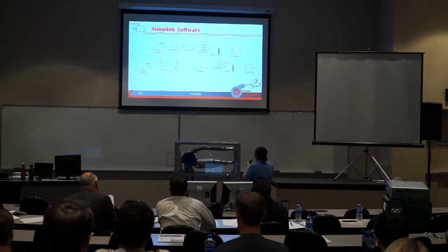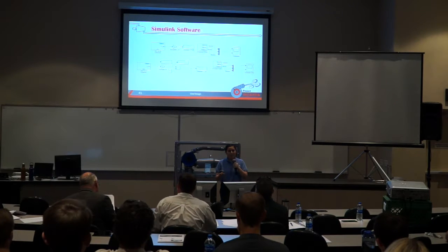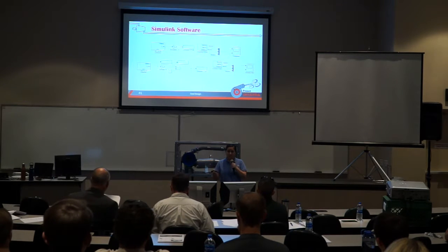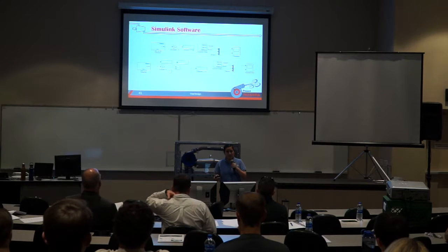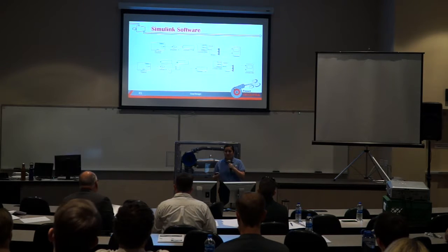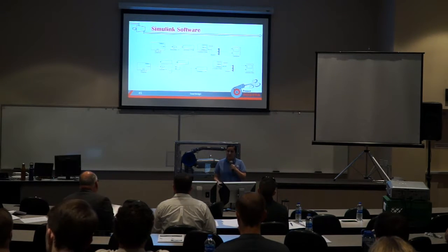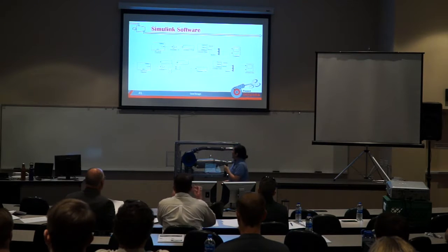These last two blocks are ones I had to make on their own. They tell us where the operating range should be, where the warning range should be, where we should start checking the system if we reach certain parameters for temperature and pressure, and lastly a shutdown range, where if it's this high we should absolutely shut down the system under any circumstances.